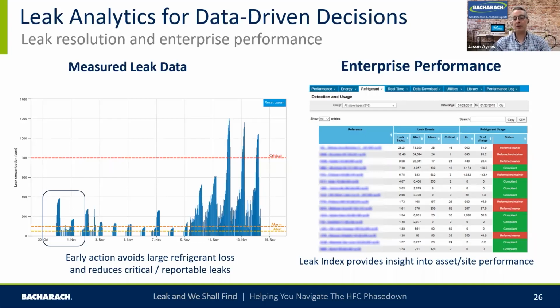Just an example of the graph here is something that we see time and time again in our Connected Solutions Bureau. We see refrigerant leaks start early and at small levels and go on for continual periods of time. These could be hours, days, or even months. At these levels, you will not see a loss of refrigerant. You won't see a system performance issue. You won't see an energy issue. But if you were to respond to these alarms much sooner, you would avoid any long-term higher refrigerant losses and reduce your overall leakage rate.